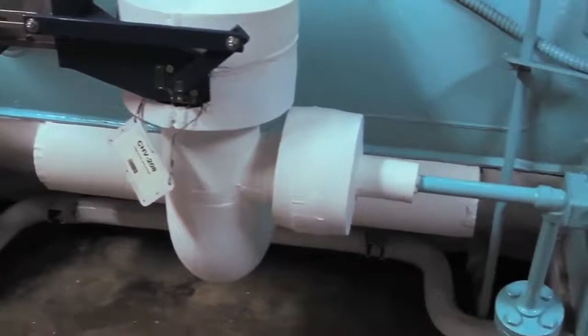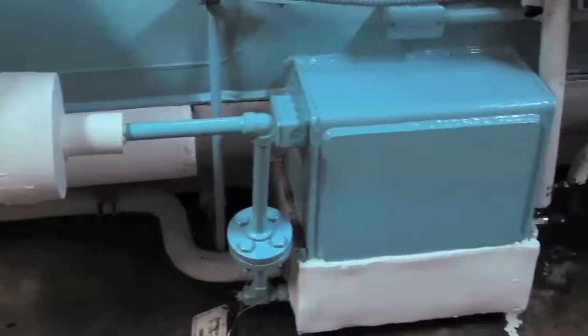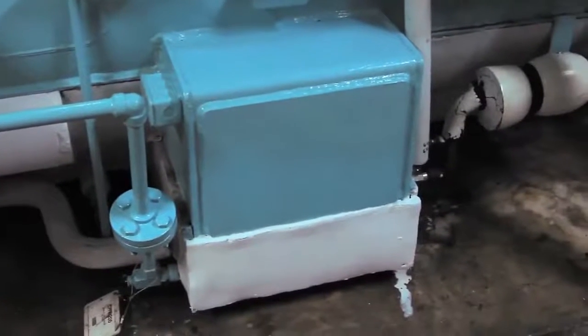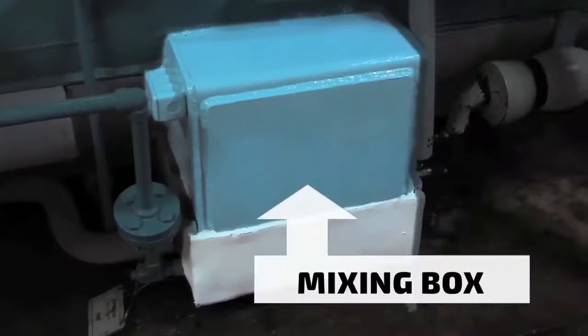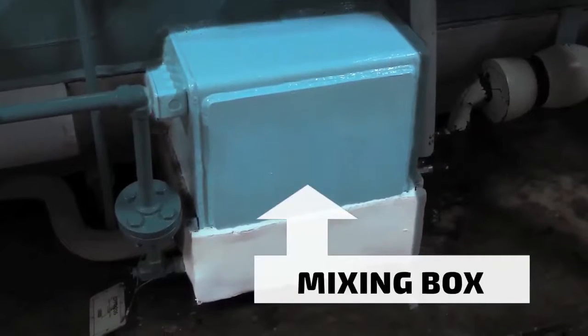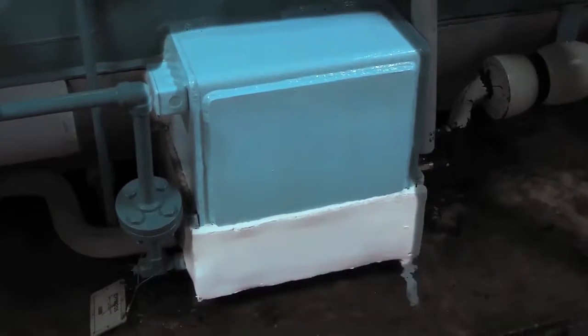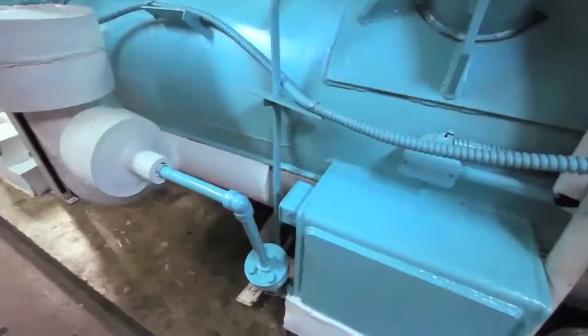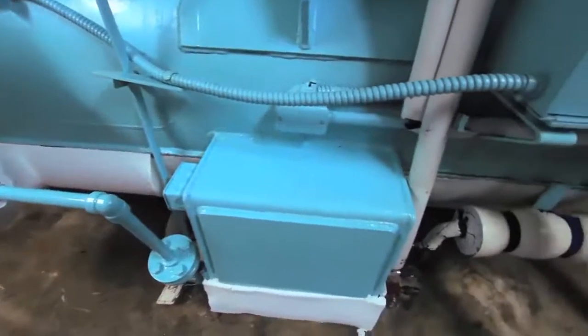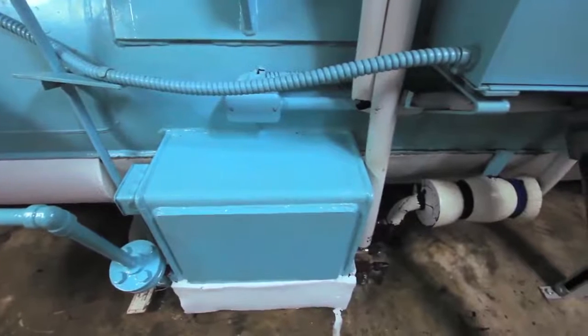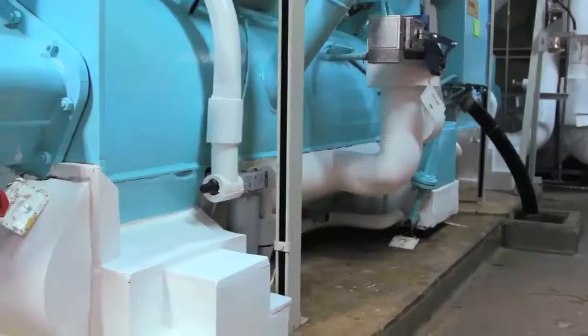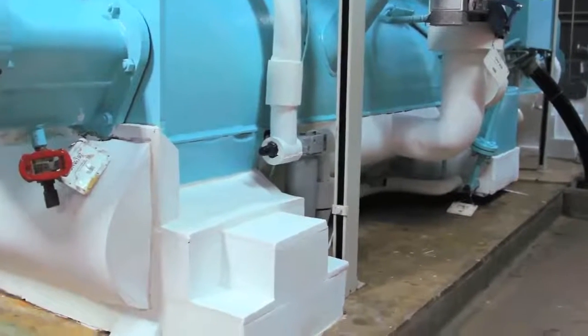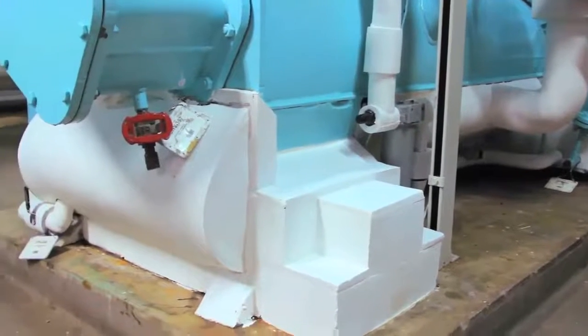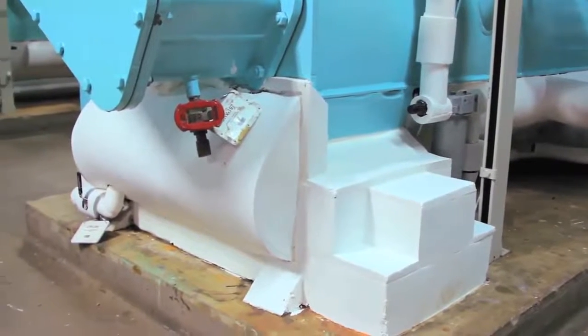This machine has a mixing box. It looks like a small box, which you can see here. There is an orifice plate inside which restricts the amount of liquid refrigerant passing through. This is the metering device. As it passes through, it changes pressure. After the refrigerant goes across the pressure breakdown device, it goes into the evaporator section.